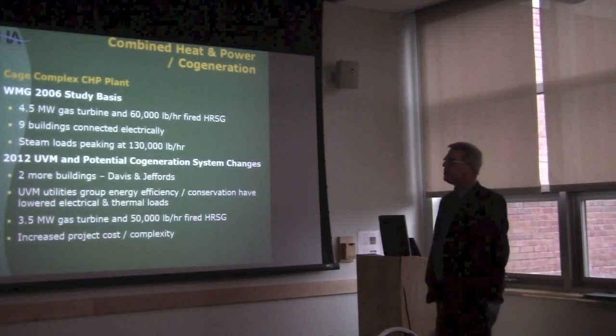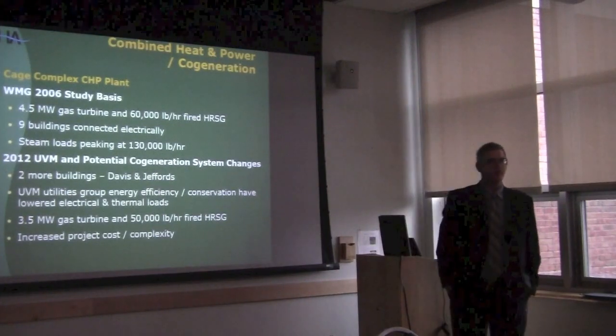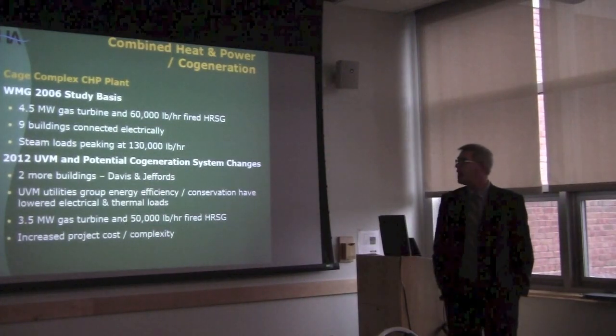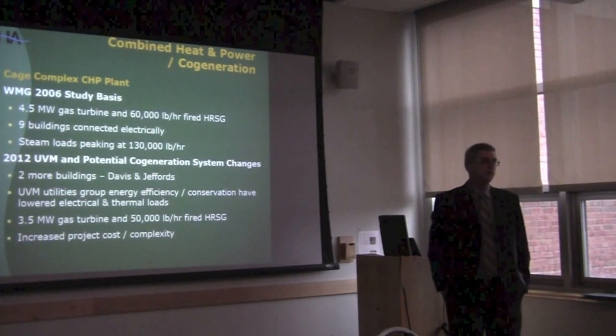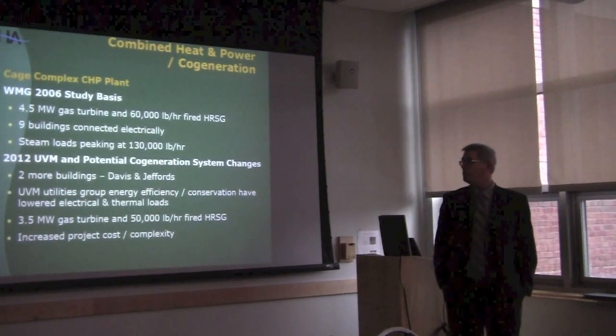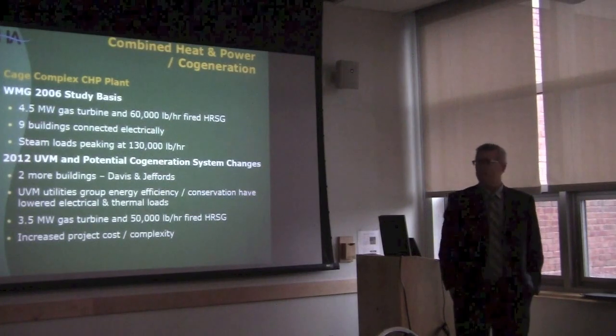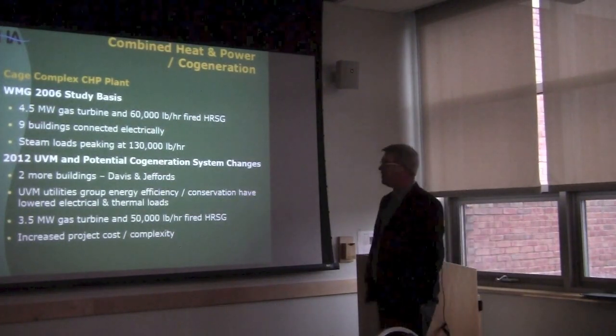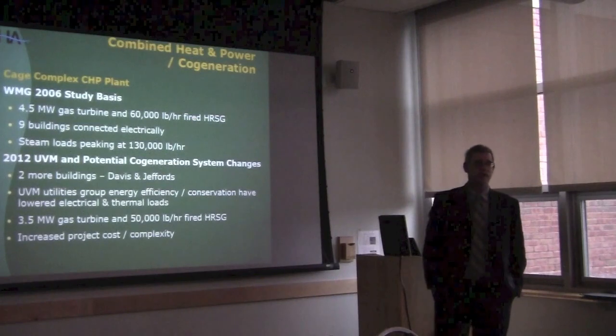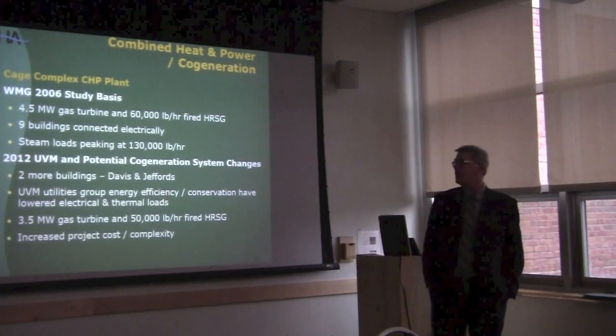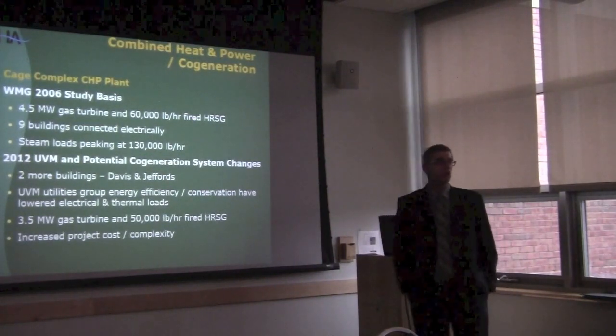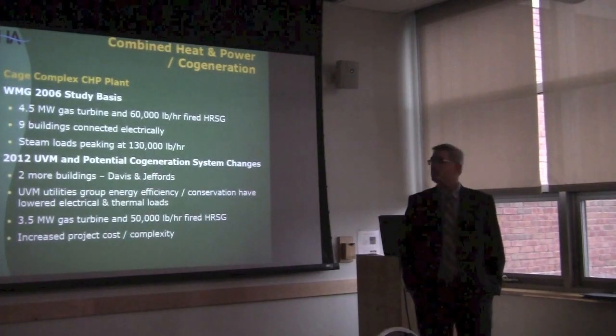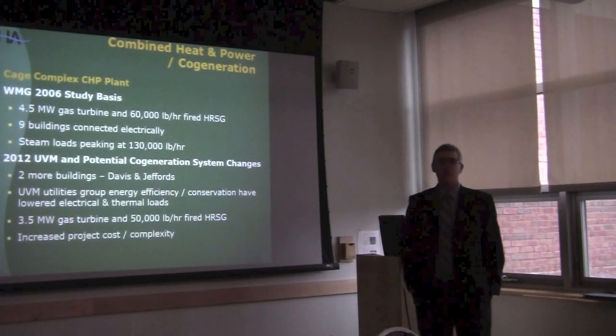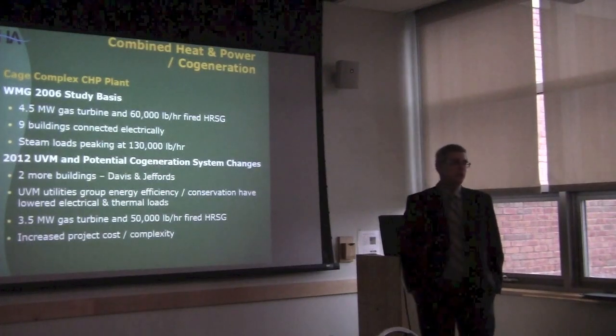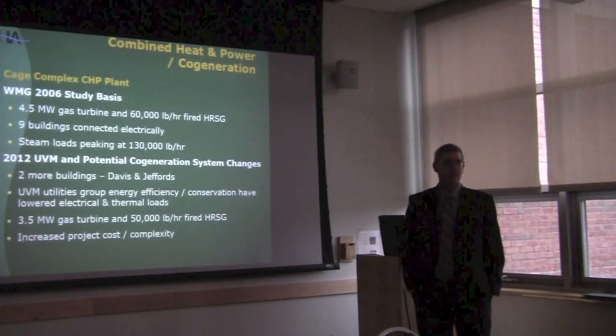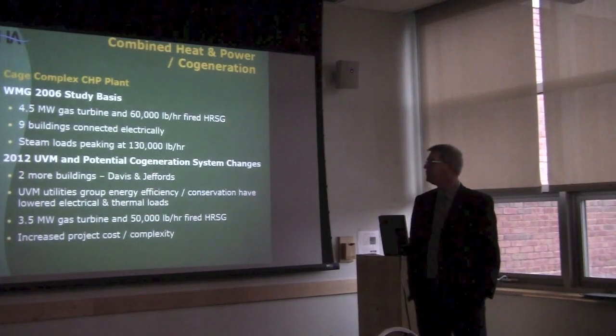One thing of interest: we're required to look at previous studies, which we did. Dave provided us with a copy of a 2006 cogeneration plant study conducted by WMG Group - as far as we can see, they don't exist anymore, but they did an extremely comprehensive analysis of cogeneration opportunities at the campus. They concluded on a 4.5 megawatt gas turbine and a 60,000 pound per hour fired HRSG. At that point there was no Davis and Jeffords building yet, and they were connecting the 9 largest buildings - we've since added 2 more.